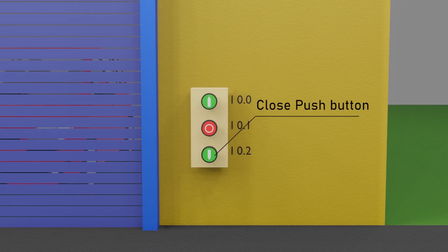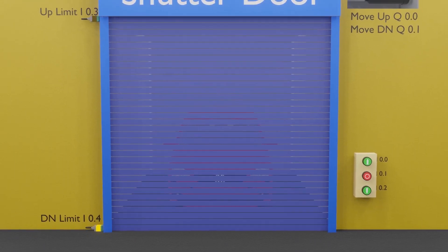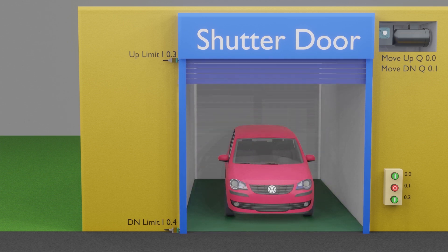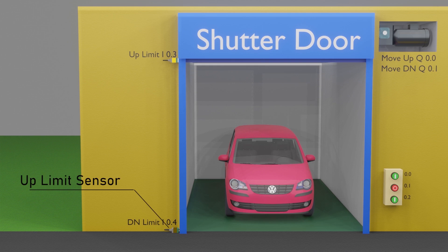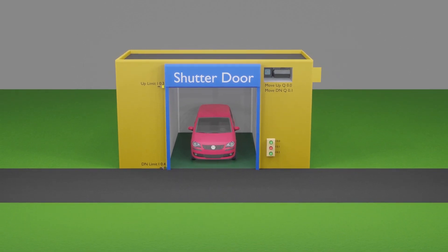Next, the close button is connected to input I0.2 of the PLC. We have also installed two sensors to detect the fully open and fully closed positions of the shutter door. When the shutter reaches the down limit, sensor I0.4 turns on. When the shutter is fully open, the up limit sensor I0.3 turns on. Now we'll open the TIA Portal software and create the program using Set and Reset commands.